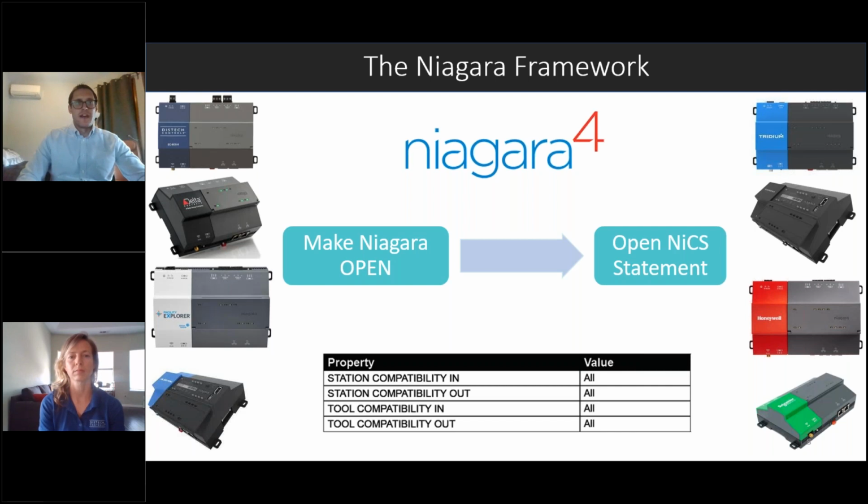You definitely don't want a vendor to lock down that controller line such that if you want to have two different manufacturers in the space, they wouldn't be able to work off of each other's Niagara controllers. And with that, I definitely recommend you mainly specify that you need an open NiCS statement, and the way you can do that is outlined in this little table that we have here.